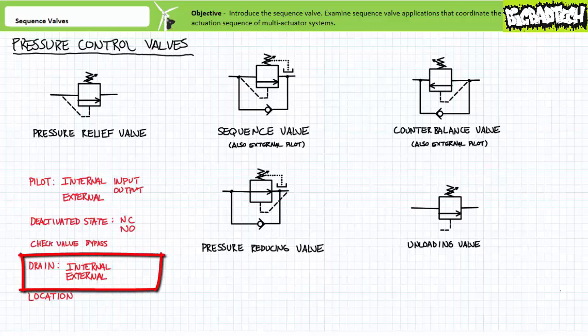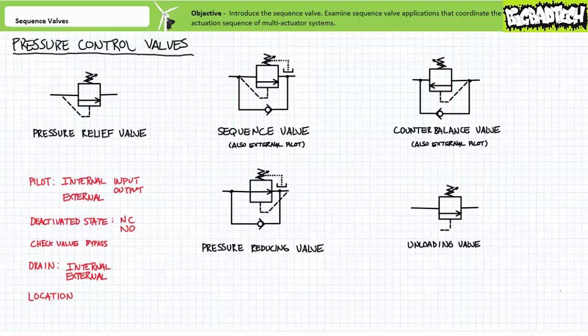Drain ports: some of these valves necessitate external drains, some of them don't. The ones with external drains, like sequence and pressure reducing valves, have pressurized secondary ports. The ones with internal drains, like pressure relief, unloading, and counterbalance valves, are intended to operate with a secondary port at low pressure, rendering an external drain unnecessary.